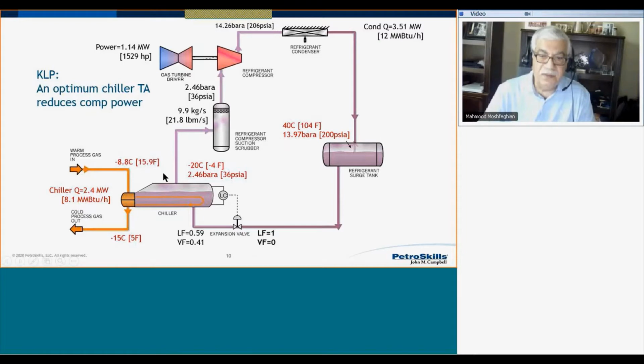So now let's discuss different items. Another item that I need to size my simple refrigeration system is the condensing temperature in the cooler here. Condensing temperature sets the discharge pressure, if I know the discharge pressure of my compressor and the delta P in my condenser. The condenser could be an aerial cooler, a water cooler, or a cool process gas stream. The condensing temperature is set by the cooling media temperature, again applying an approach temperature. But before I go into much more detail, let's explain the different types of equipment we utilize and see the actual photos, and we proceed to complete this section.